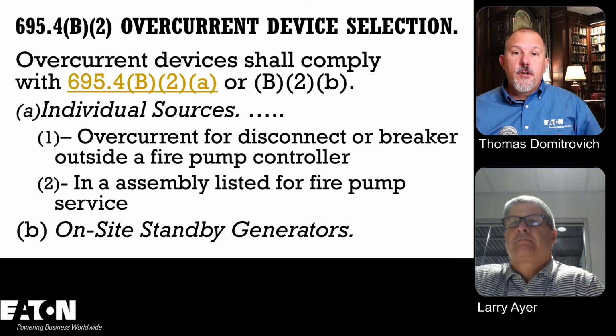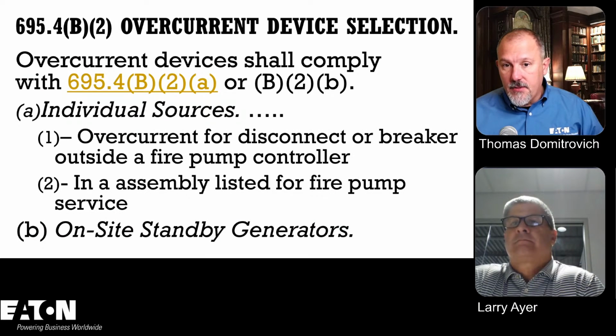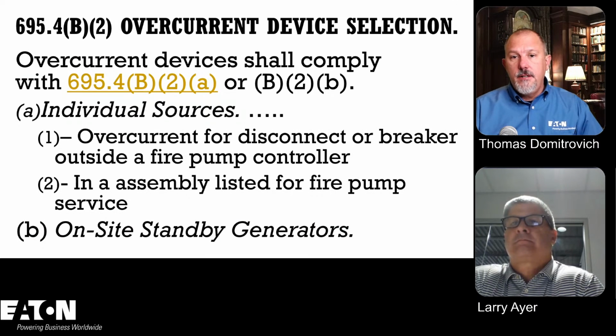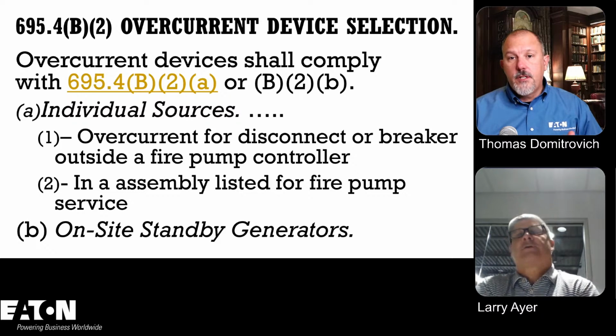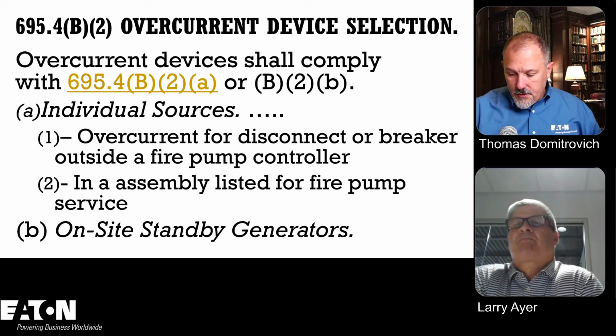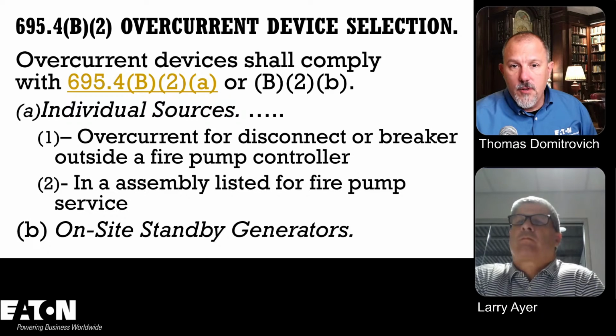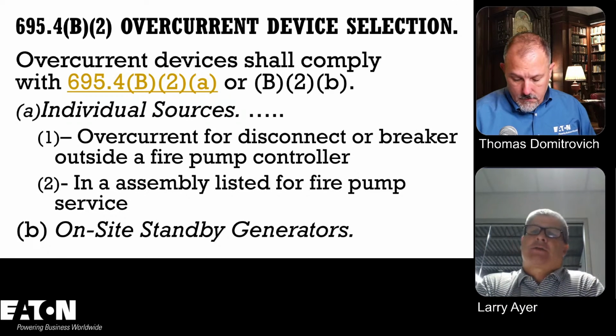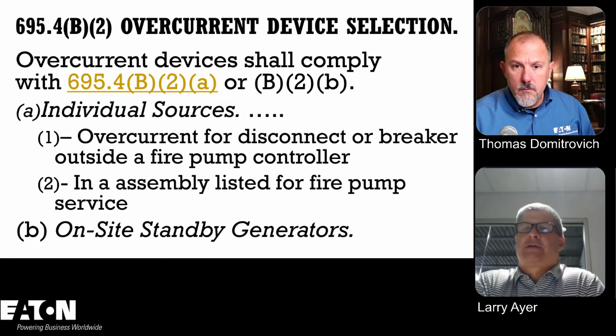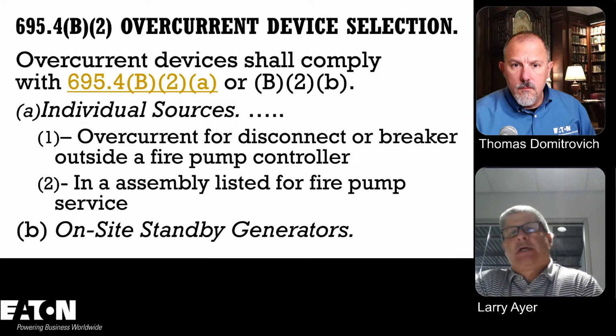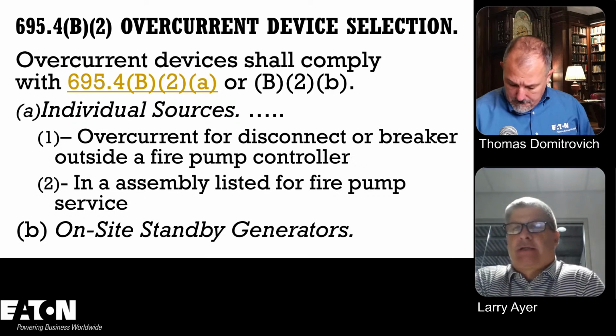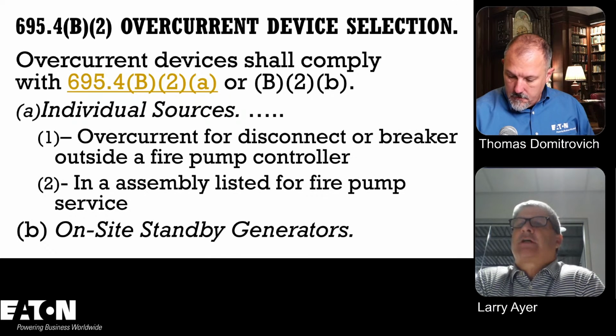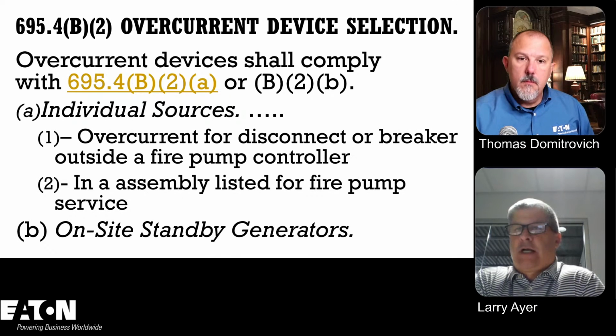Now this is picking your overcurrent device. So we already talked a little bit about this, right? So this is just your instantaneous, just your no overload protection, basically. Right. So you look at this, you have two ways to size the overcurrent protection. It splits between A and B. A is for individual sources and B is on-site standby generator. So you have to look at this in two different ways.